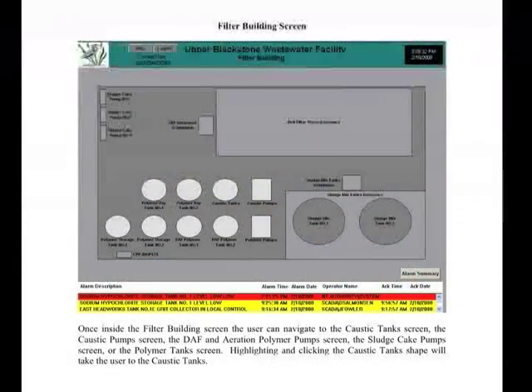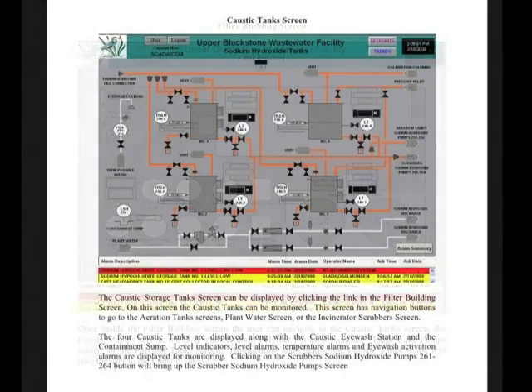If you were to click on the filter building, you get to the next page, which is page 11, which is the filter building overview screen, and it shows you things like your belt filter presses, your polymer, your caustic, your mix tanks, your swing pumps, that type of thing. That's all shown here. If you're on this screen, you have a couple of different shapes that say caustic. One says caustic tanks, one says caustic pumps. We're going to start with the caustic tanks.